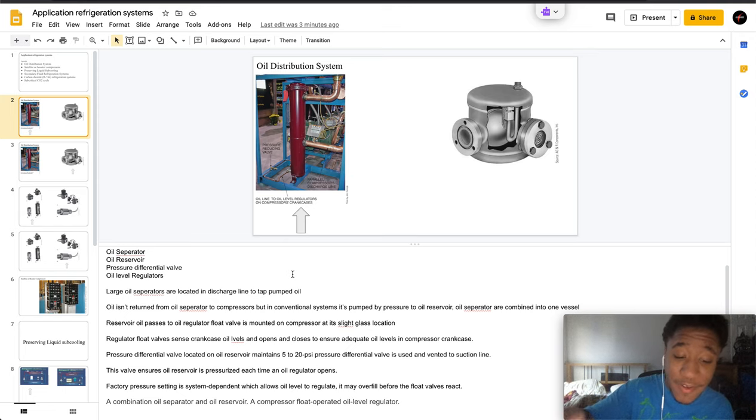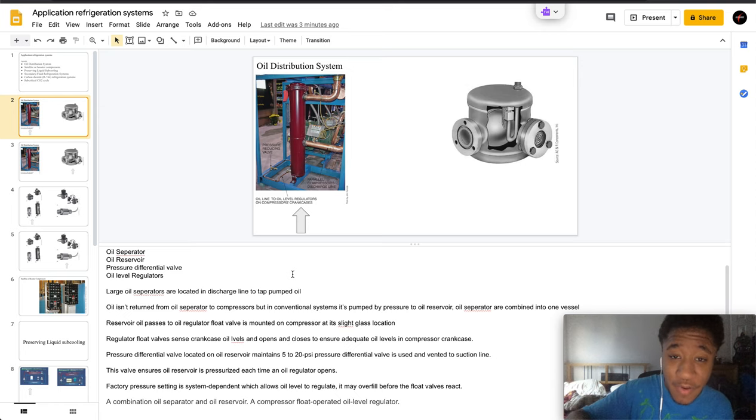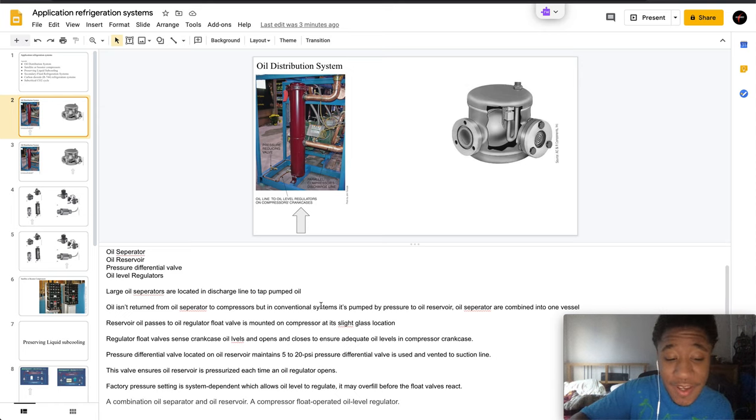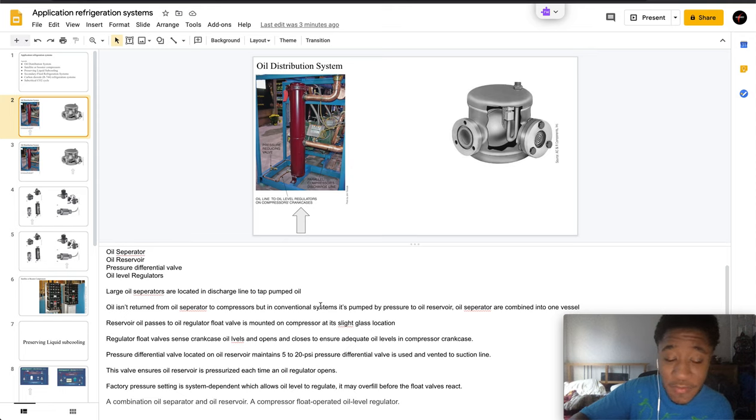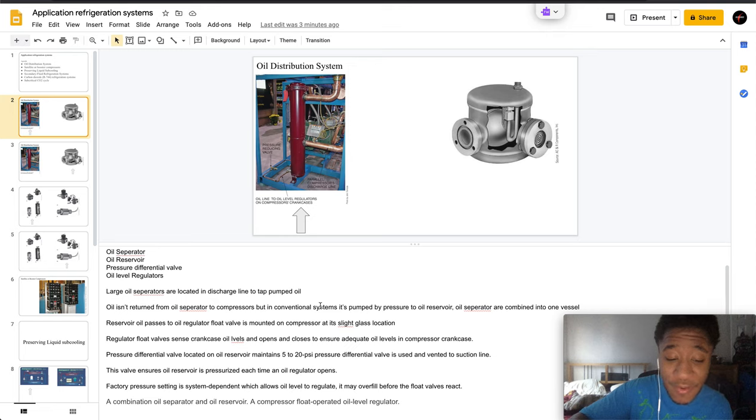The oil regulator float is mounted on the compressor at its sight glass location. The regulator float valve senses the crankcase oil levels and opens and closes to ensure that adequate oil levels are in the compressor crankcase.